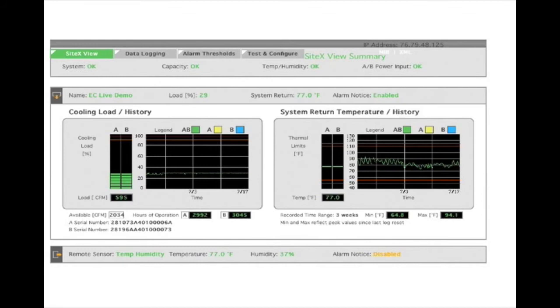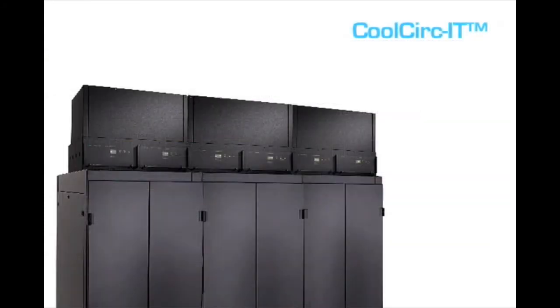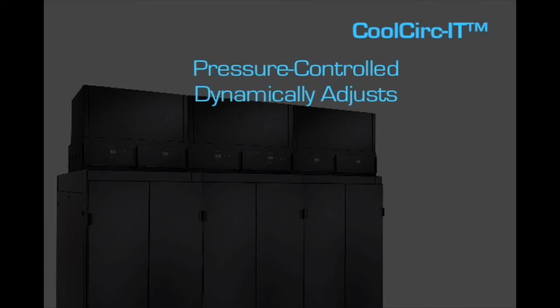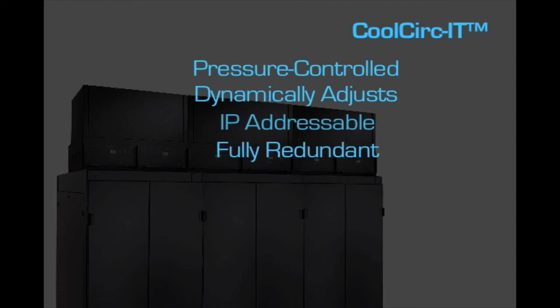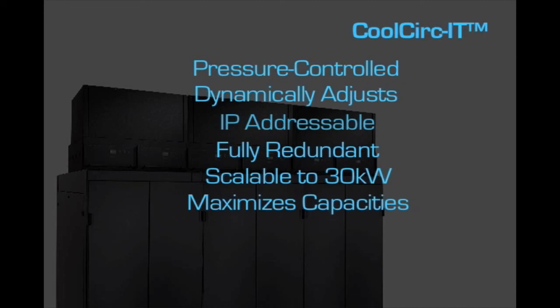Additionally, CoolCirc-IT can attach to most racks and can communicate with existing management software, so it can be deployed without disrupting operations. In summary, CoolCirc-IT is a pressure-controlled, active, high-density heat containment system that dynamically adjusts air volume to maintain zero pressure in each rack. It's IP addressable with user-defined SNMP traps and alarm thresholds, and is fully redundant with hot swappable fan modules and dual power inputs. The units are scalable to 30 kW and work to maximize capacity of existing cooling infrastructure.